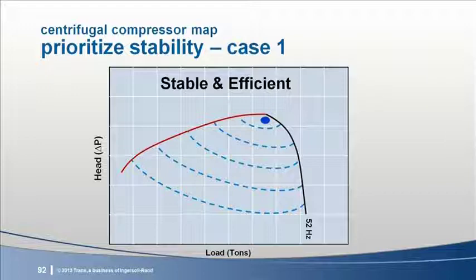It's important to note that the most efficient operating point for the compressor is tucked up as close as possible to the surge line, right on the edge of surge. This discussion of why this is true is beyond the scope of this E&L. There are other presentations available that explain this in some detail.